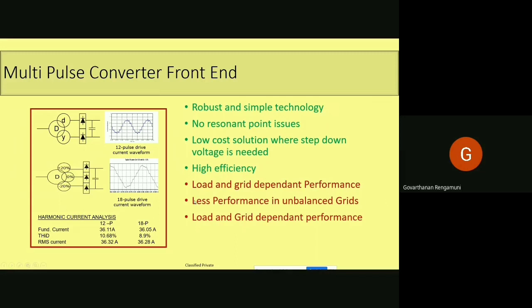However, even though there are some advantages, there are disadvantages also in these techniques. Load and grid dependent performance, less performance in unbalanced grids, because in a balanced grid it works good, but if there is an unbalance based on the load and based on the construction, the harmonics will vary. And the load and grid dependent performance, as I already mentioned, load will affect the harmonic levels, and the grid impedance will also play an important role here. So these are all the different techniques that can be used to eliminate the harmonics produced by a 6 pulse variable frequency drive.